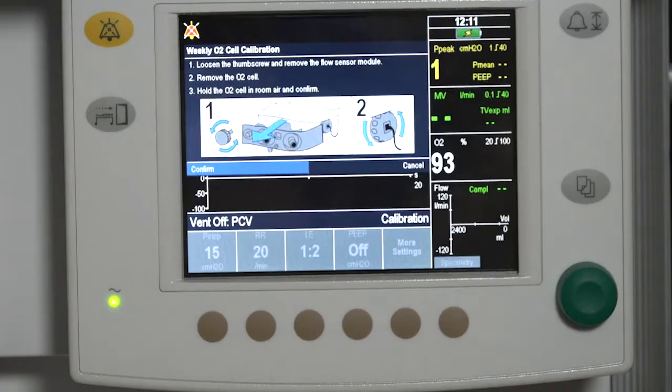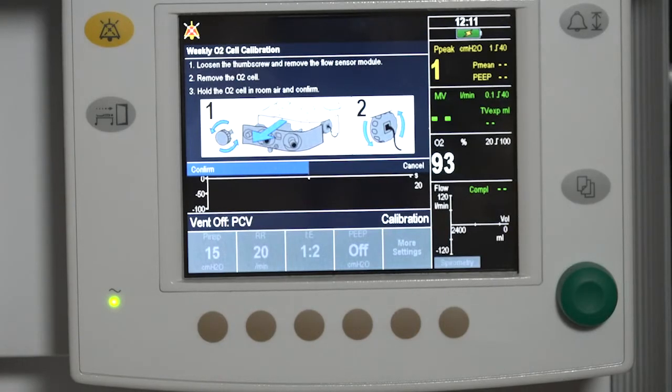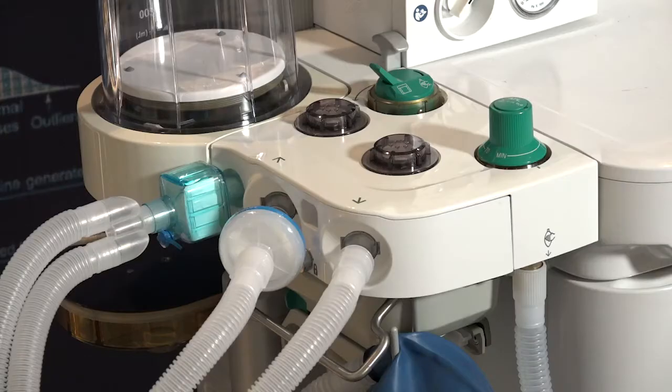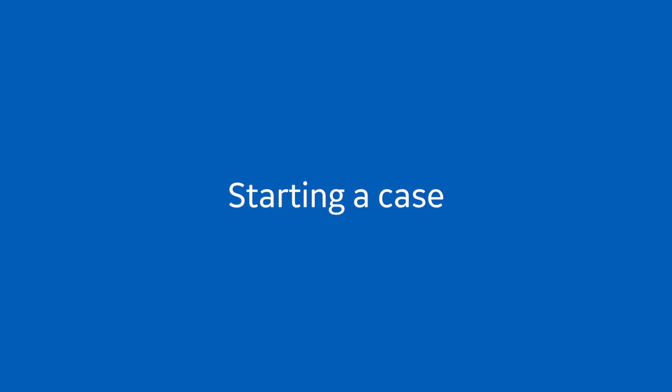Perform a full test after changing the patient tube type. Changing the patient breathing circuit after completing a ventilator leak test affects the volume measurements in all modes.